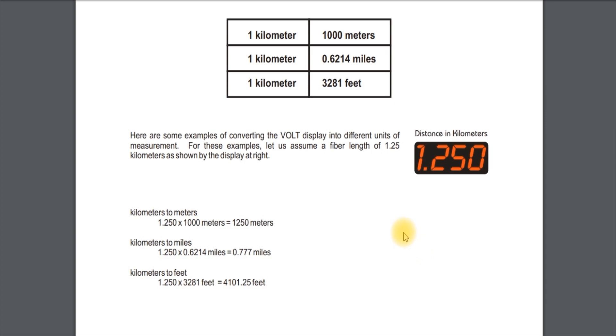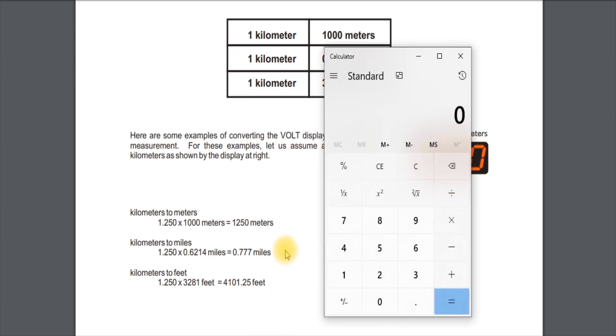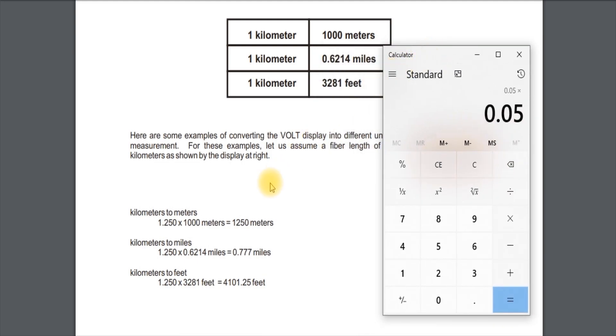So what we need to do to figure out how long our cable is, we need to take the measurement that we had, which was the distance in kilometers, .050. That's what we had. And since we're doing feet, we're going to times it by feet. So let's see here, .050 times 3281. So our tester's telling us that this cable is 164 feet, pretty much.